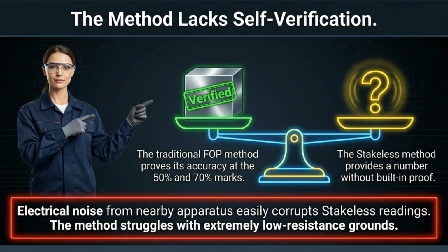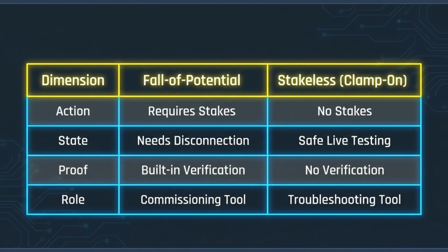The stakeless method lacks the self-verification of the fall of potential method. Additionally, electrical noise can easily corrupt readings, and the method often struggles with extremely low resistance grounds. To summarize, while fall of potential is a commissioning tool that requires stakes, the stakeless clamp-on method serves as an excellent troubleshooting tool for live systems.